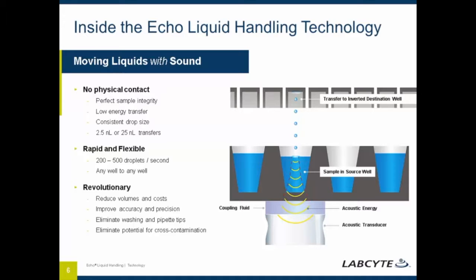The drop travels upward. Because we control the power being applied to the meniscus, that drop is consistent drop after drop, and the drops come out very fast — up to 500 droplets per second — so you can build up large transfer volumes very quickly. People often worry about fluid slipping or leaking from the inverted destination plate, but because of the capillary forces within the well, that doesn't happen. The ECHO has been used for a variety of reagents and applications without any dripping issues.